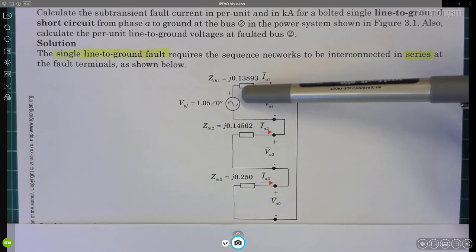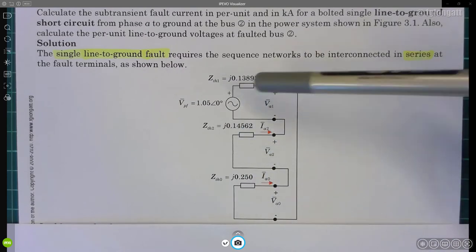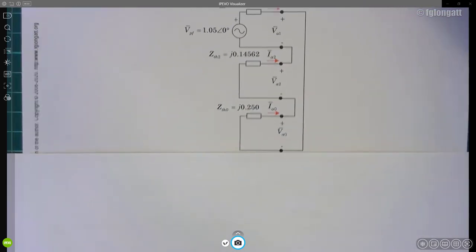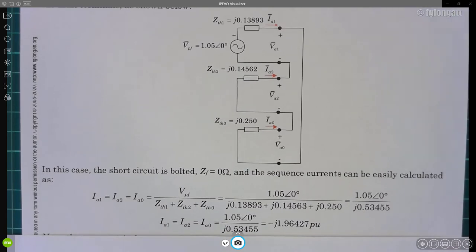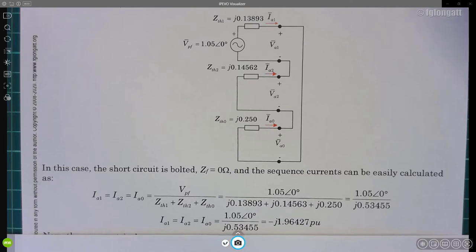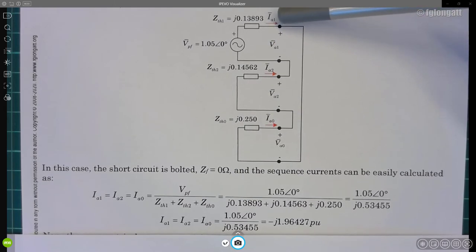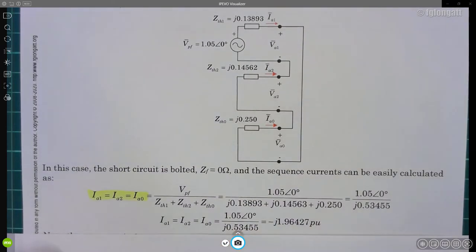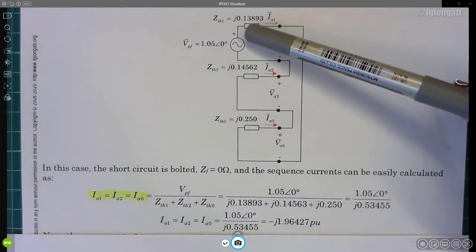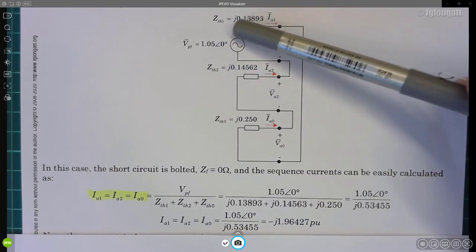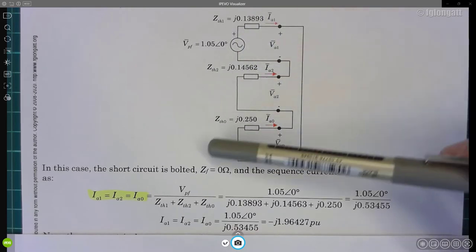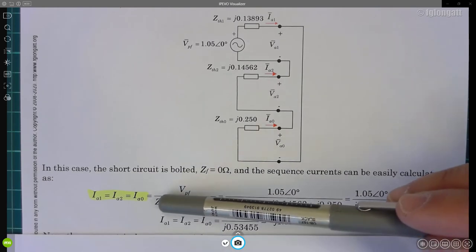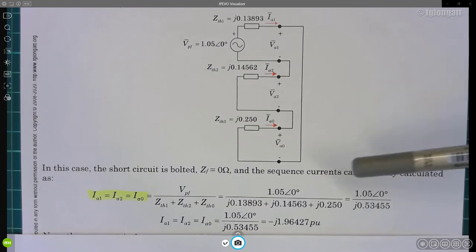With the series sequence interconnection, there is a beautiful property: the positive, negative, and zero sequence currents all have the same value, and we can calculate them using basic circuit analysis. The configuration is straightforward — just a series circuit. For a single line-to-ground fault, all three sequence currents are equal, and the current equals the unique voltage source in the positive sequence network divided by the total impedance, which is the sum of the Thevenin impedances for positive, negative, and zero sequence.